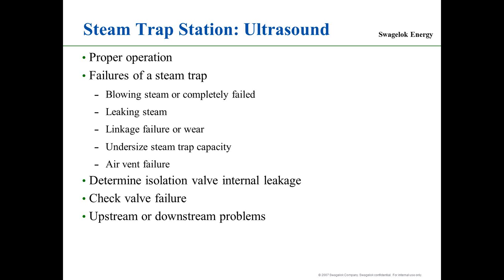Undersized: one of the failures of steam traps is sizing. The ultrasound gives me the ability to determine the sizing because I'm looking at the cycle times and discharge times and things like that. So it really gives me the ability to see if the steam trap is sized correctly. An undersized steam trap will wear itself out in a very short period of time and cause premature failure. It also gives me the ability to check air vent failure on one particular design of steam trap called the F&T, which I'll get into.